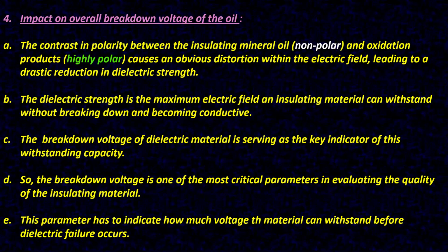Number 4, impact on overall breakdown voltage of the oil. The contrast in polarity between the insulating mineral oil, which is nonpolar, and oxidation products, which are highly polar, causes an obvious distortion within the electric field, leading to a drastic reduction in dielectric strength.